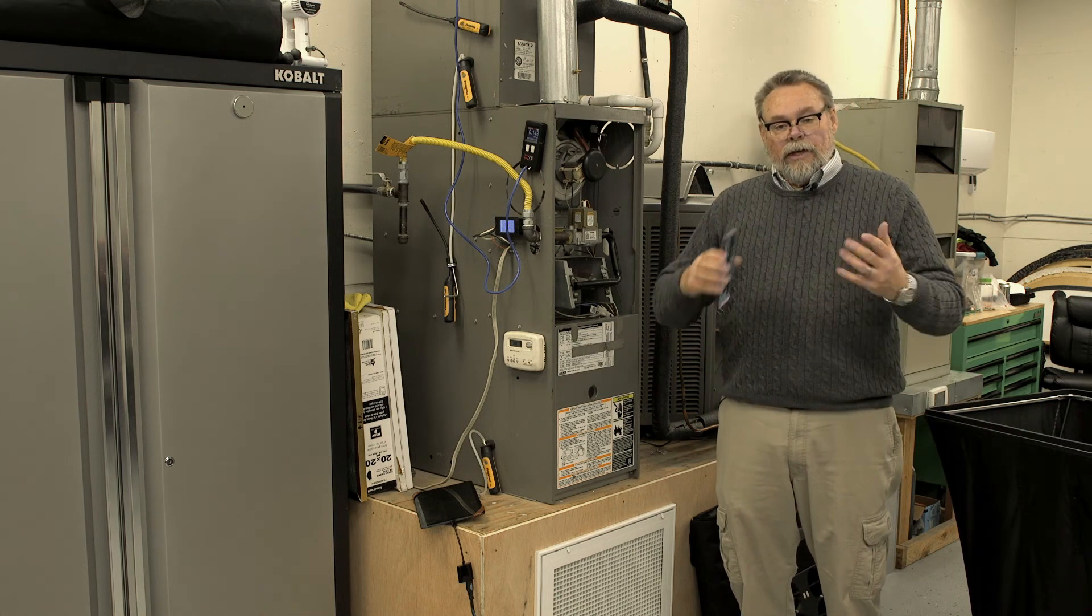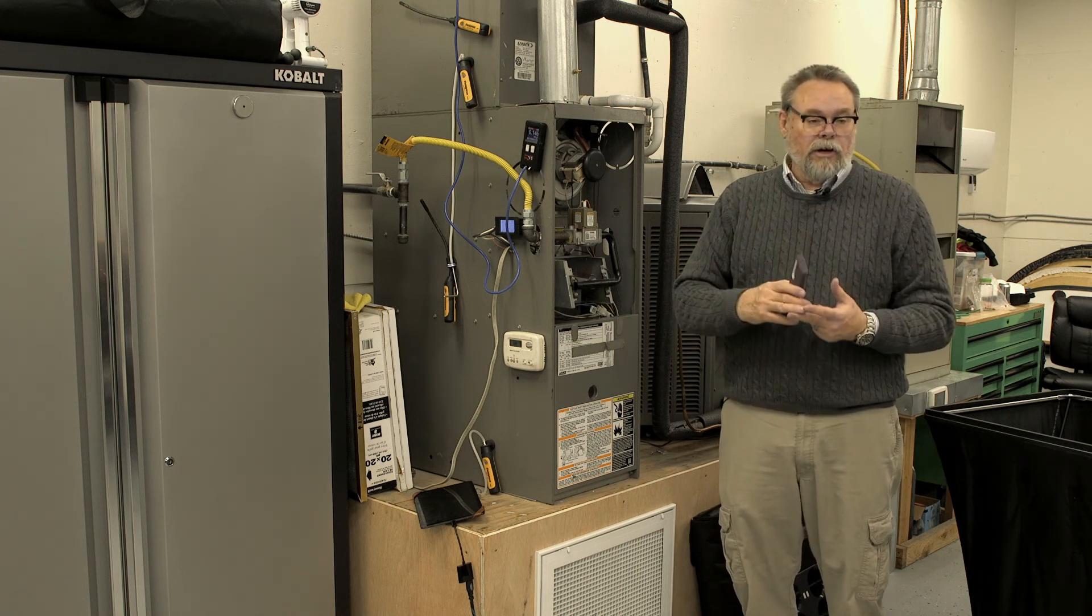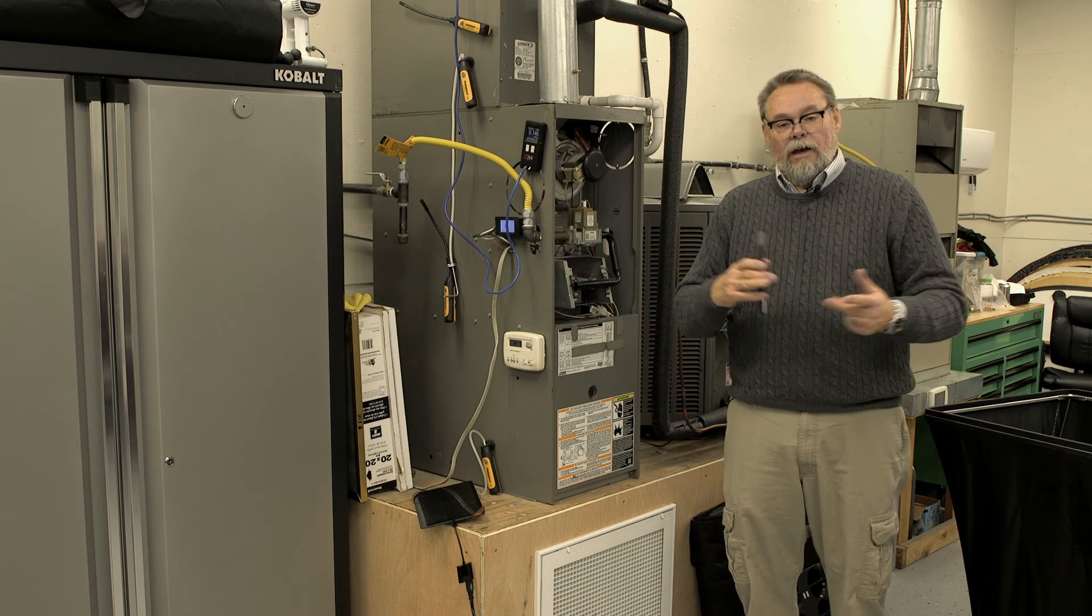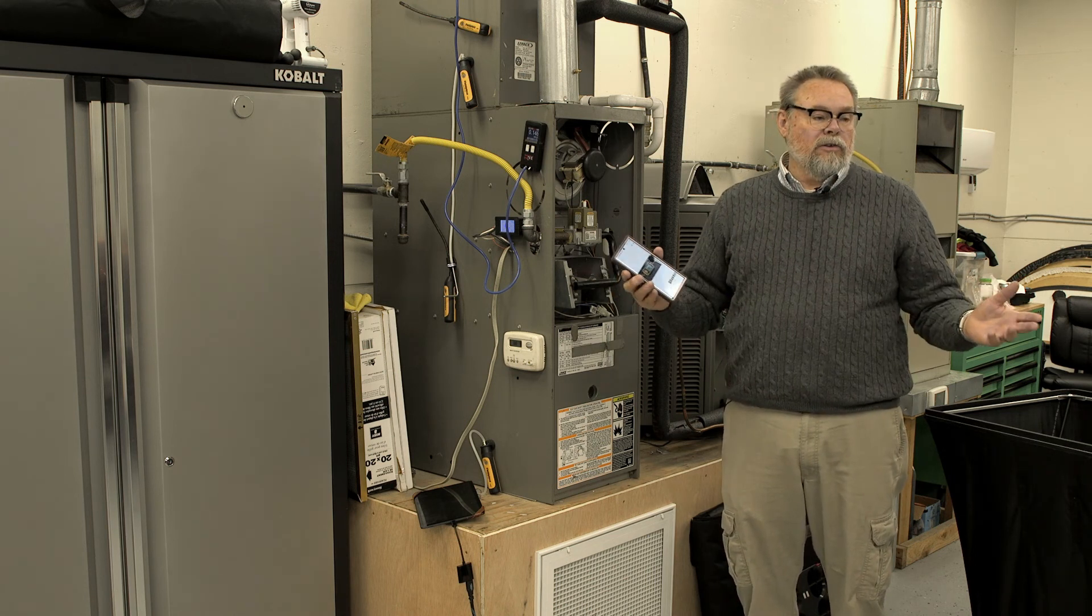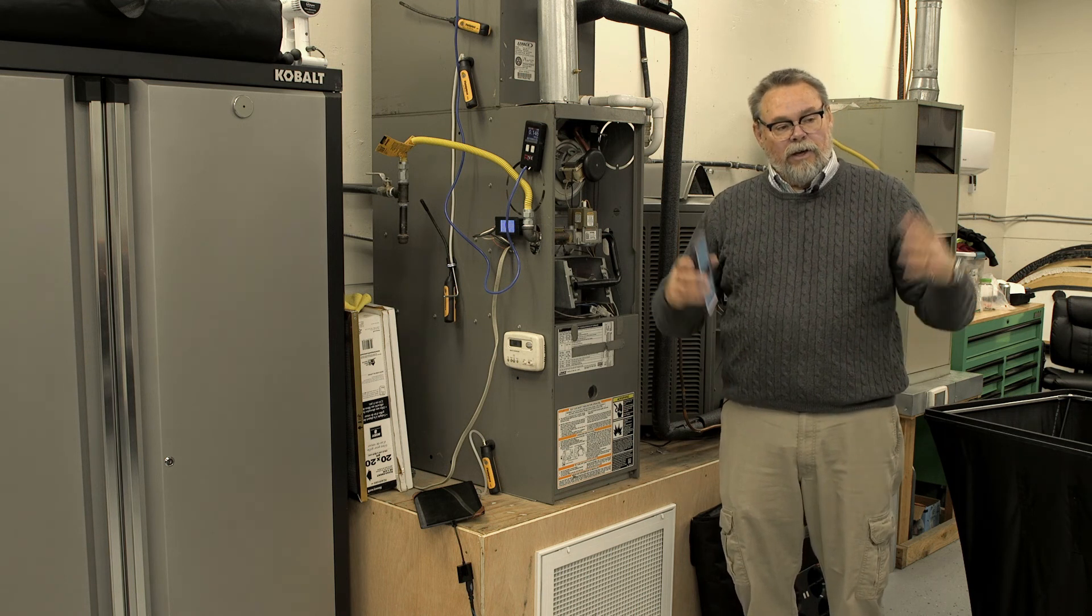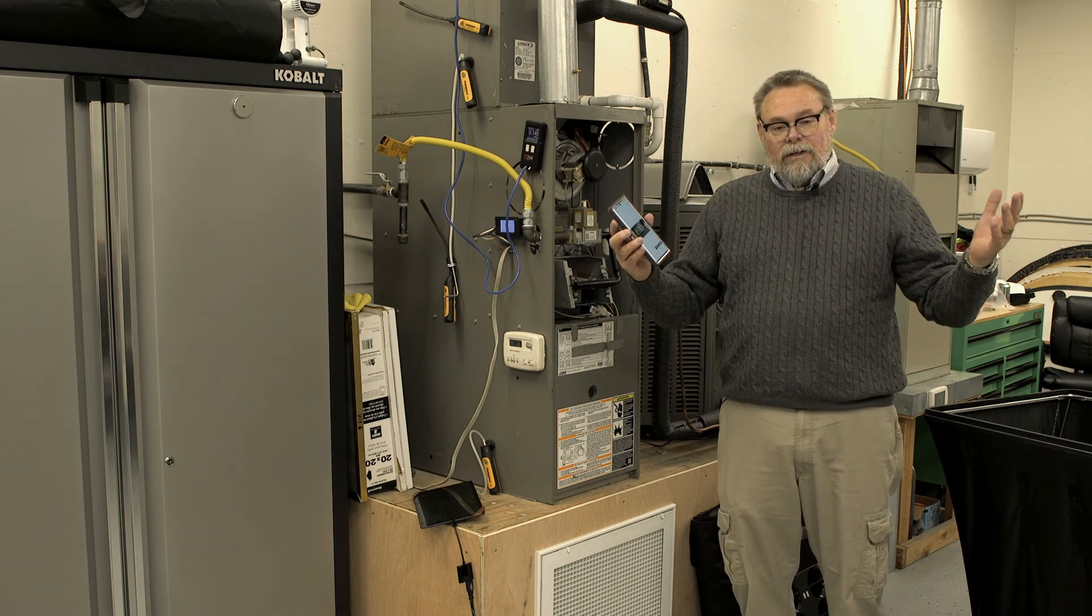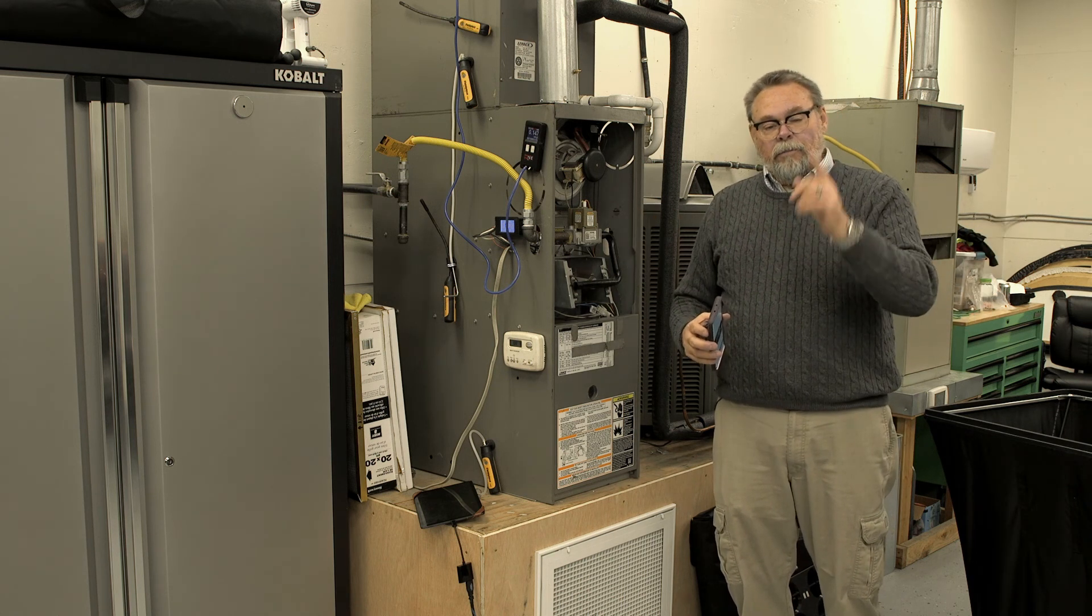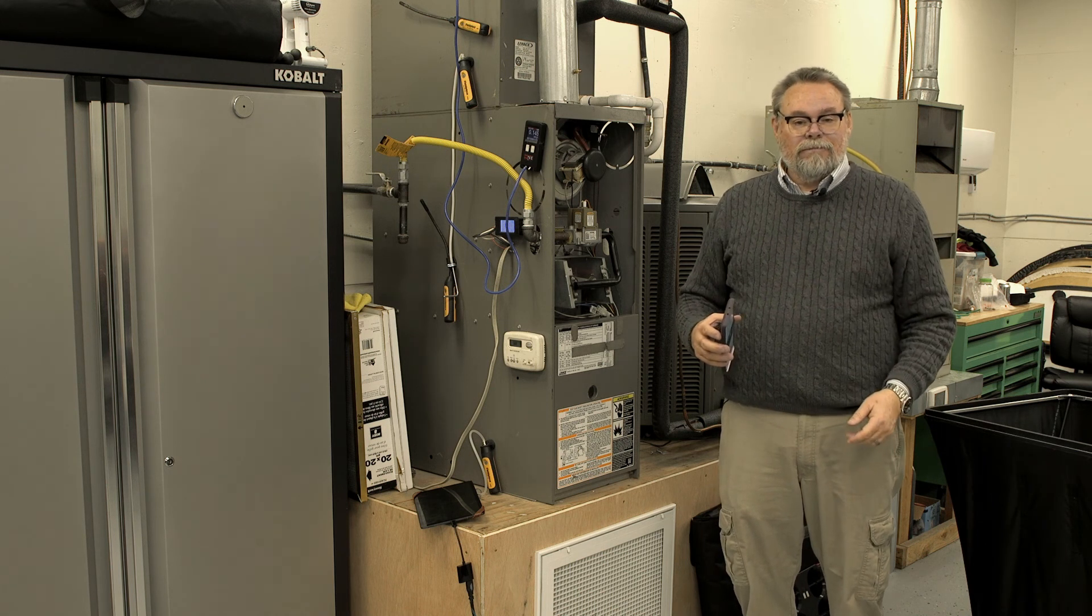So next time you're out in the field, take these measurements, get your static pressure, get your airflow through the system, measure the difference in temperature, TD, and temperature rise, and then multiply out and get your BTUs. CFM times 1.08 times delta T will give you your BTUs per hour that the furnace is producing. All right. Well, thanks for watching and please like and subscribe and stay tuned for the next video. Thanks again.